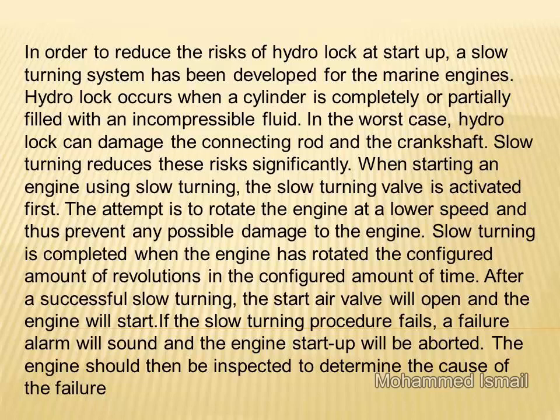After a successful slow turning, the start air valve will open and the engine will start. If the slow turning procedure fails, a failure alarm will sound and the engine startup will be aborted. The engine should then be inspected to determine the cause of the failure.